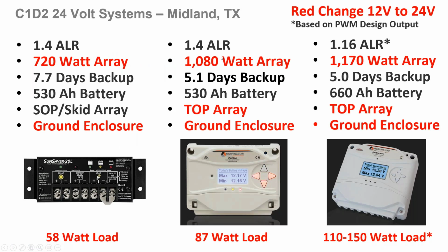Highlighting some of the changes from the 12 volt to the 24 volt configuration in red, you'll see that the array doubled going from 12 volt to 24 volt. Therefore our load doubled, but our battery capacity also doubled, and therefore our enclosure solution needs to move from a pole mount to a ground mount in a different design. Similarly, on the ProStar PWM, we're moving from a 3 module array to a 6 module array, which pushes us up to a different style array for a top of pole format. Both of these now go to ground enclosures, and the array doubles in size.